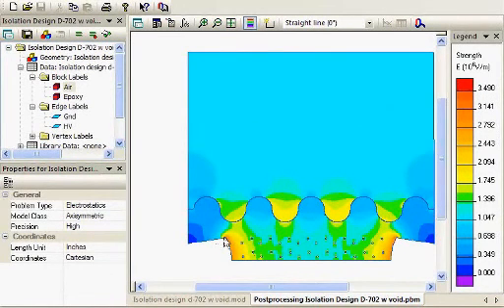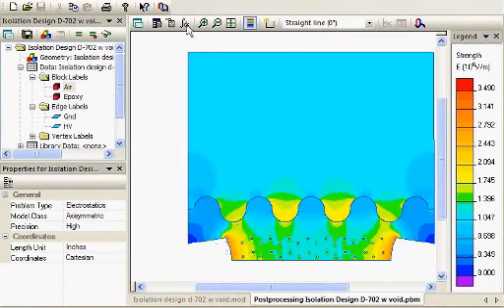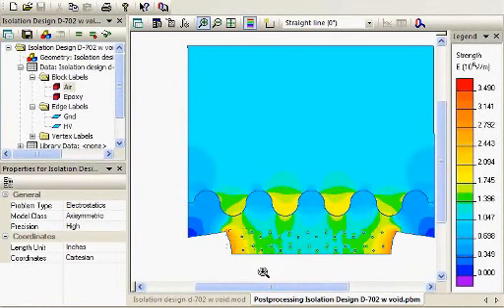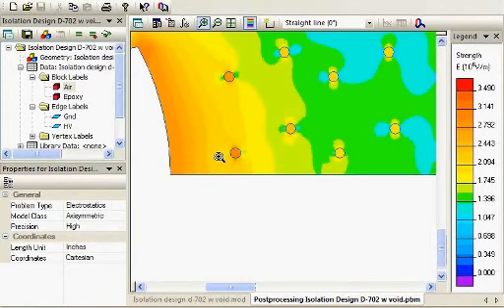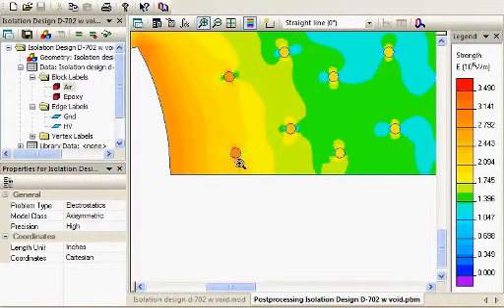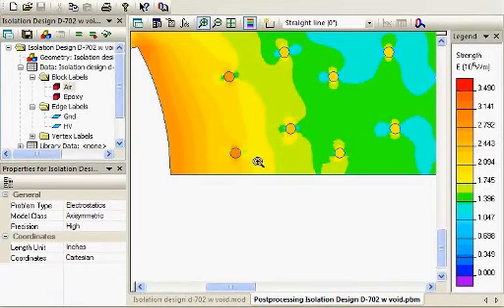And, you can see the fields are a little bit higher now, even at the edge of the insert. But, what we also want to look at is what's happening inside these little voids or areas within the solid dielectric. And, you can see they're at a higher field strength than the surrounding areas.